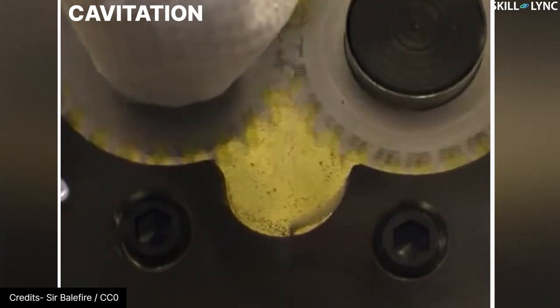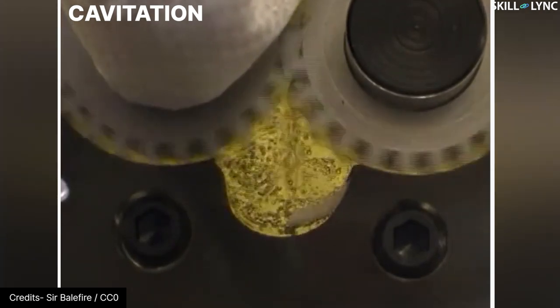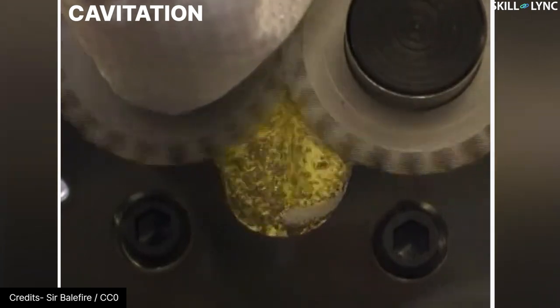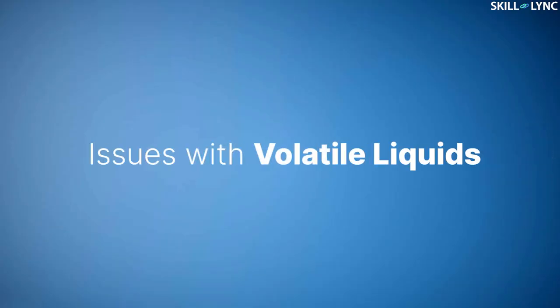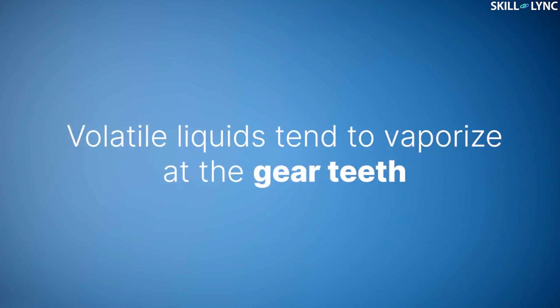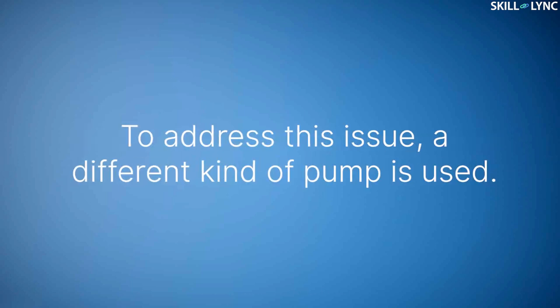Gear pumps are not without disadvantages. Increasing the RPM of the pumps higher than the prescribed value for a fluid can lead to cavitation. The pumps also have issues when pumping volatile liquids. This is because volatile liquids tend to vaporize locally as gear teeth spaces expand. To address this issue, a different kind of pump is used.